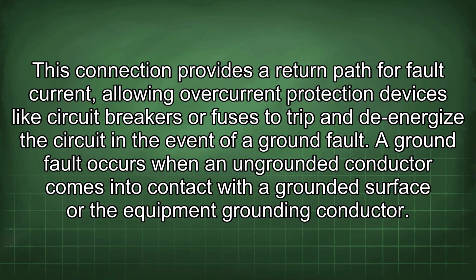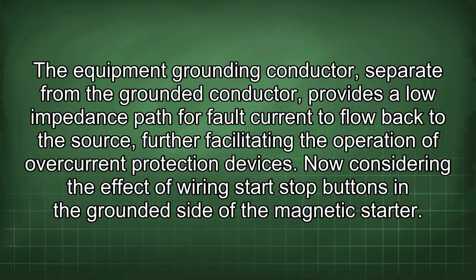A ground fault occurs when an ungrounded conductor comes into contact with a grounded surface or the equipment grounding conductor. The equipment grounding conductor, separate from the grounded conductor, provides a low impedance path for fault current to flow back to the source, further facilitating the operation of overcurrent protection devices.